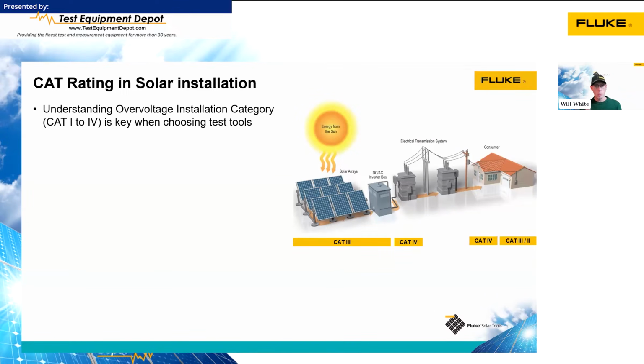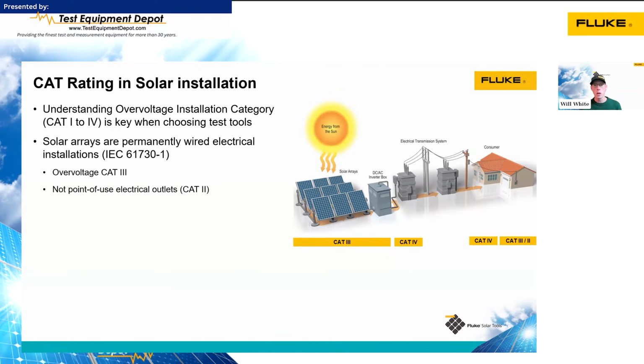So how do we know if it's going to be able to withstand that? The first thing we need to know is the category or CAT rating. There's categories 1 through 4. I'm going to start with the most hazardous one, which is category 4. That's the closest that we're going to be testing to the utility. That's our point of interconnection, our meters, our main service disconnect, medium voltage transformers.